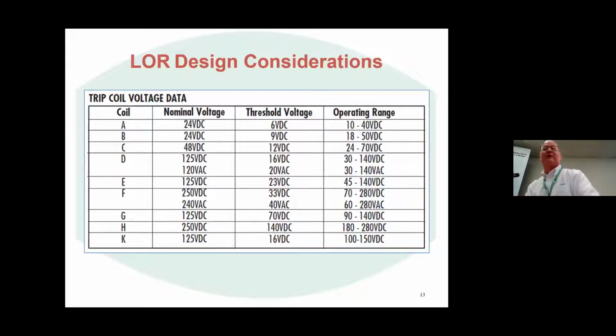And you can see at the 125 volt DC level, I've got a couple of options for a 16 volt DC minimum threshold voltage that will still trip the device, or a 23 volt DC voltage that will still trip the device. It will just trip it in a longer period of time if it's not at the nominal 125 volt DC level.